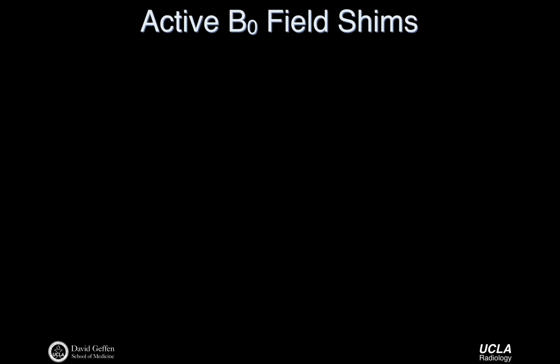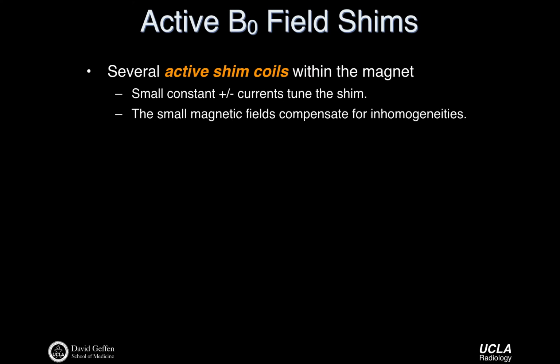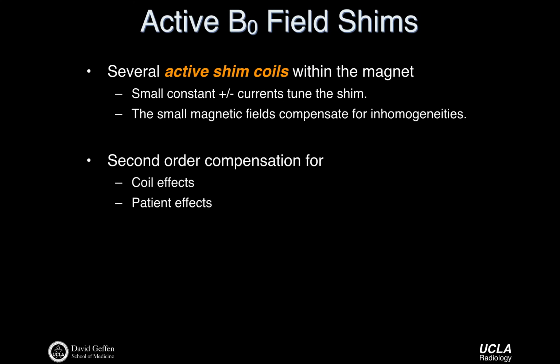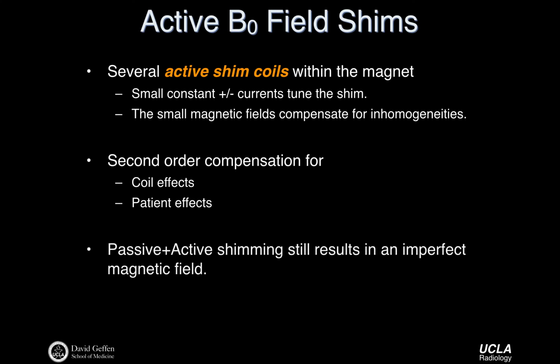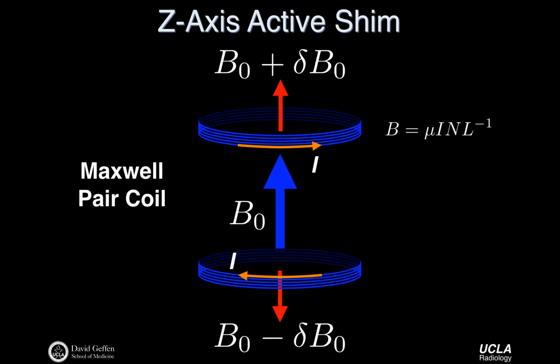That's right. I just said that the field's still imperfect even with the use of active and passive shimming. So in this next slide, this is just saying, if I have a big solenoid that generates my B0 field, I could also build a system that has some additional solenoid elements. I could add some current to this element or this element, and I could manipulate the magnetic field inside, at isocenter. These are just the so-called active elements.